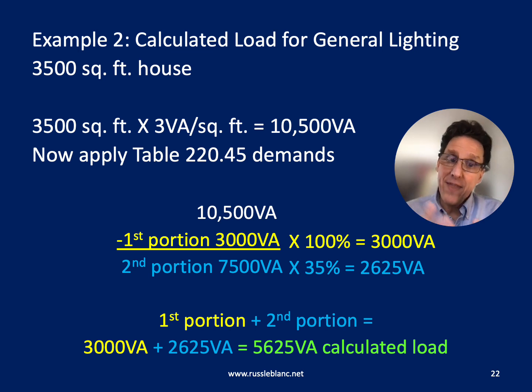And so you would add that load, the lighting load, to all the other loads in the house, right? A range, if there's a range, an electric dryer, all the appliances, all those things get added together when you're sizing the service or the feeder, right? This is only the lighting portion.